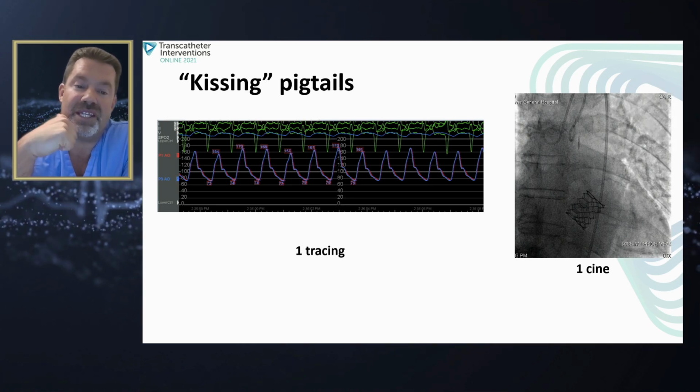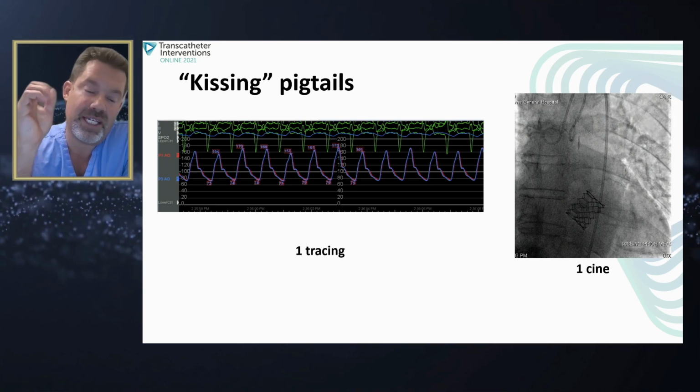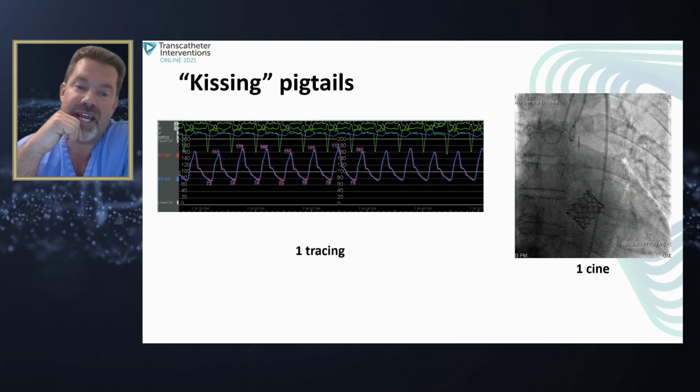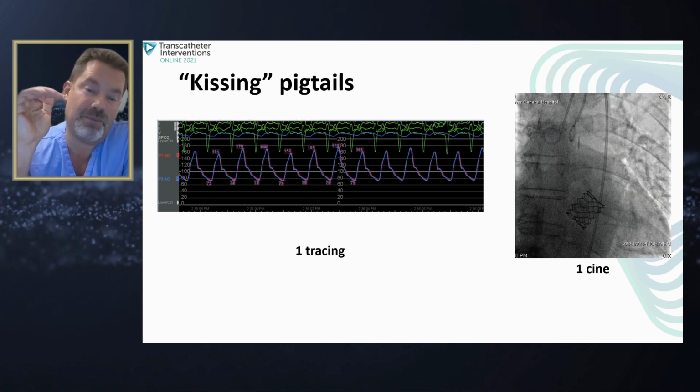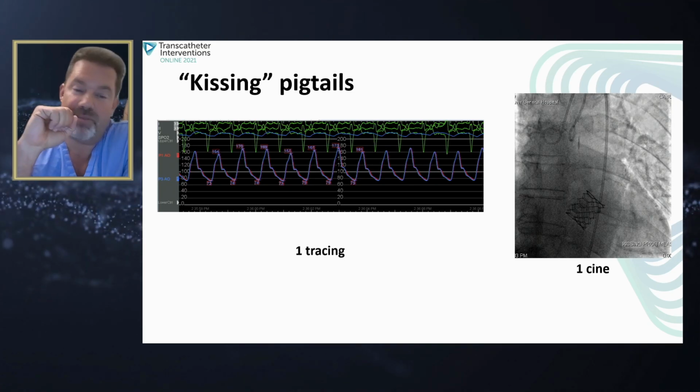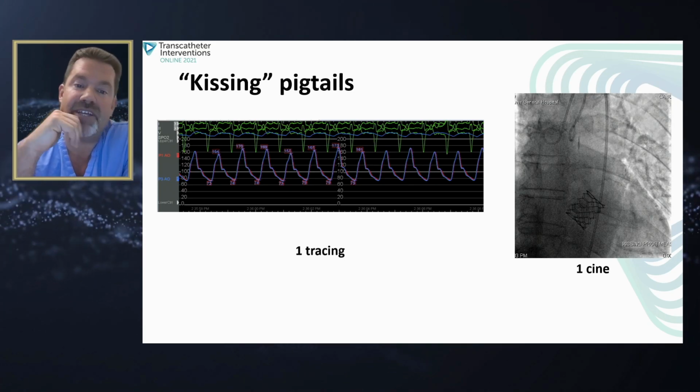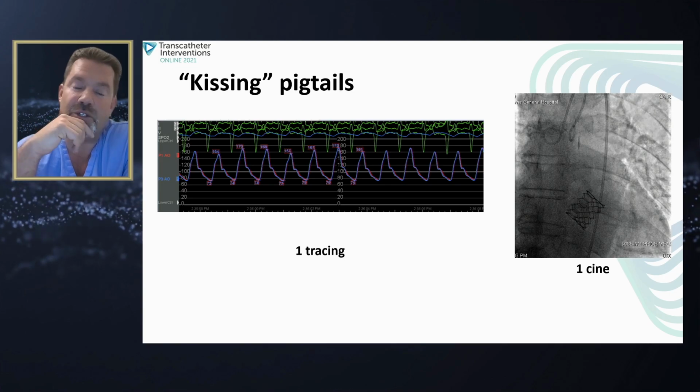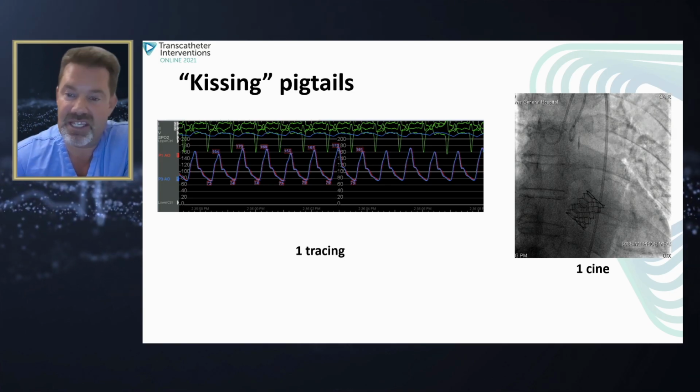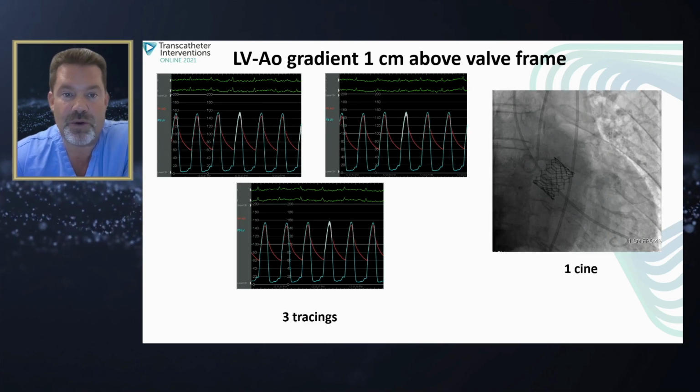Again, this is just to make sure your systolic is within 2 millimeters of mercury. Everything is zeroed and leveled. We actually come up with a CT-derived height from your CT scan, which we all do pre-TAVI, so we know where to set your transducer on your table. Very easy, very quick. We cross.